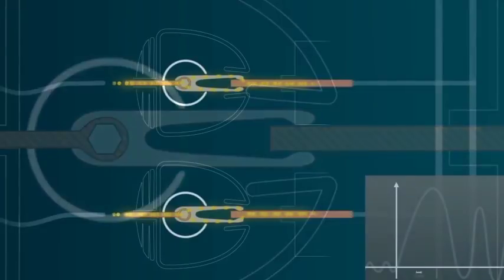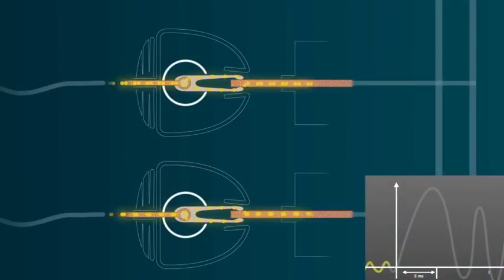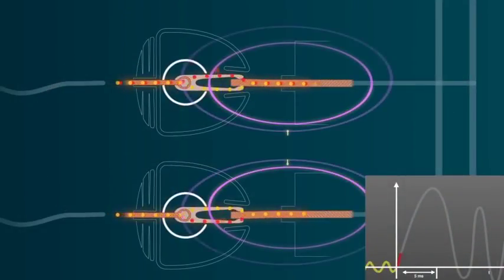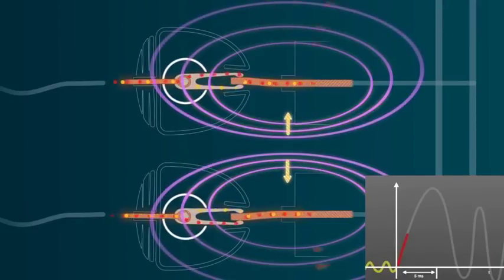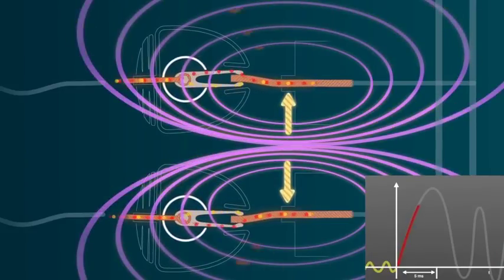The magnetic field between the vertical bus bars is responsible for the conductors shaking, in just one interfering effect that may lead to malfunction of the finger contacts.